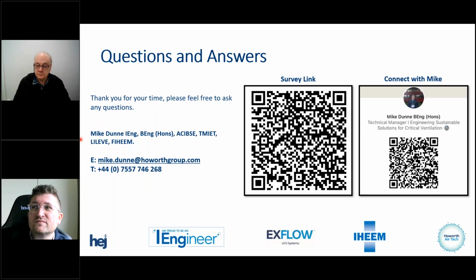In the last 12 months we've gone belt and braces on that again, particularly on validations. So if you go to HTM03 Part B, look at Chapter 3, there's I think 140 questions about the air handling unit, its environment, the plant room. They're the minimum standards, and that was a recommendation given to us by an authorised engineer for ventilation. When we were told that, we were thinking, oh my God, another 140 questions we need to do. However, it's proved really good for us in validation, because validation in HTM isn't a snagging exercise, it's an exercise to check the system has been correctly commissioned, designed, installed, and is fit for clinical use. However, I use it as a snagging exercise too, to start a conversation with the main contractor or the installer of the air handling unit, and the Chapter 3 checklist is a really good thing that helps me collate that snagging list at the front of the document.